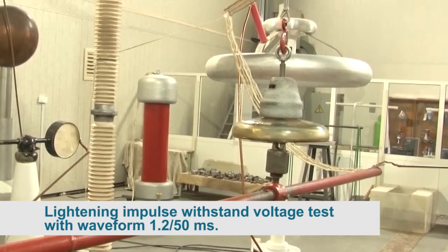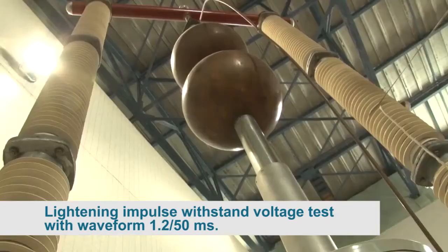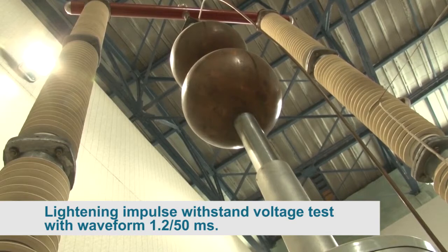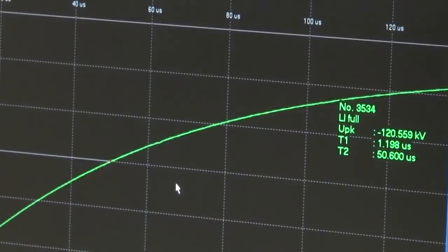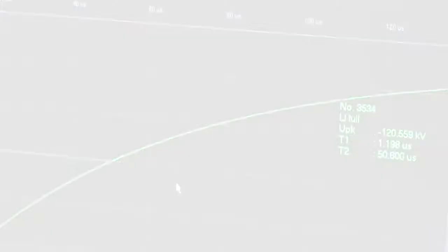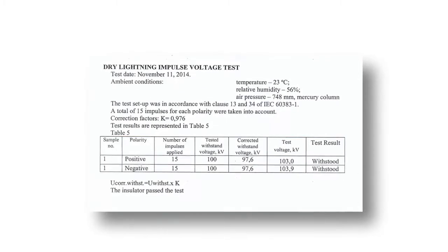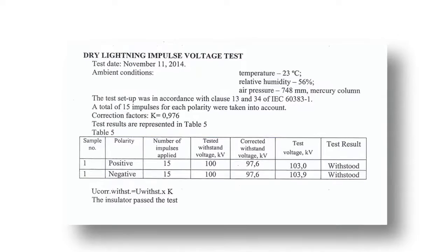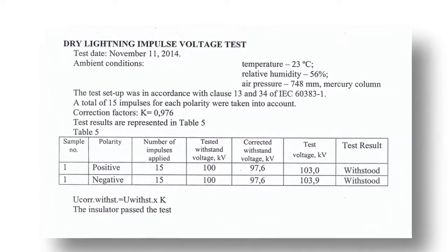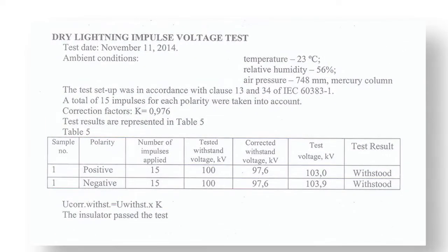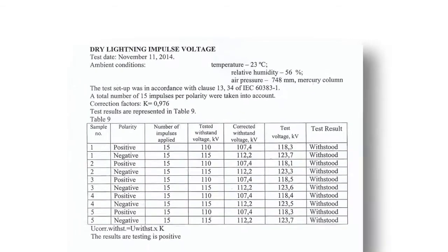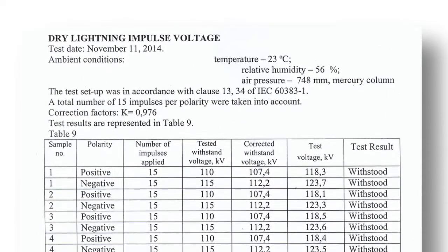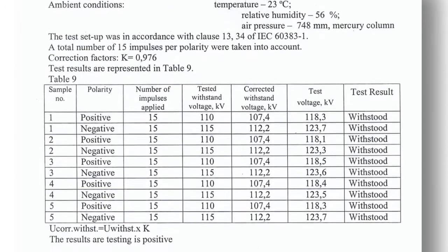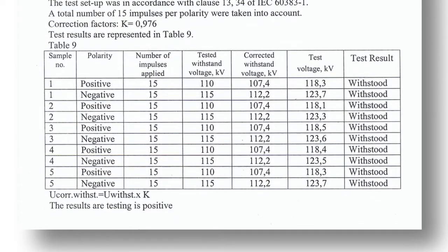Lightning impulse withstand voltage test with waveform 1.2 per 50 microseconds. Dry insulators should withstand standard lightning impulse voltage of both polarities. The value of the test voltage for the insulator type PS12A is 118.3 kilovolts, and for the insulator of type PS70E is 103 kilovolts. Standard withstanding voltage for the insulator of PS70E is 100 kilovolts. 15 impulses were applied. Testing voltage is 103 kilovolts. The insulator passed the test. The insulator of type PS70E meets the IEC requirements. Insulators passed the tests. No flashover and puncture have occurred.